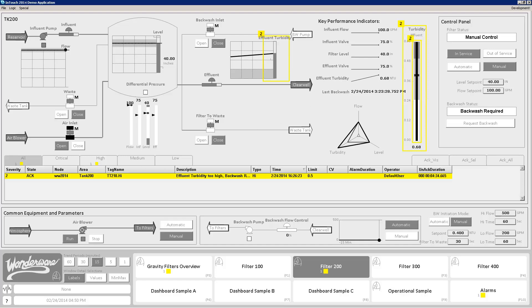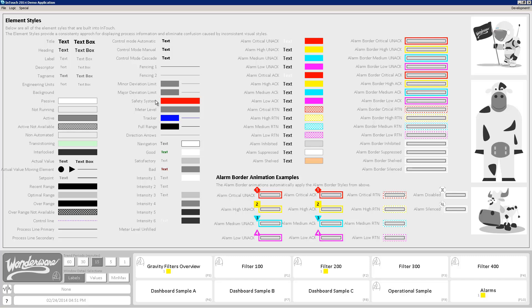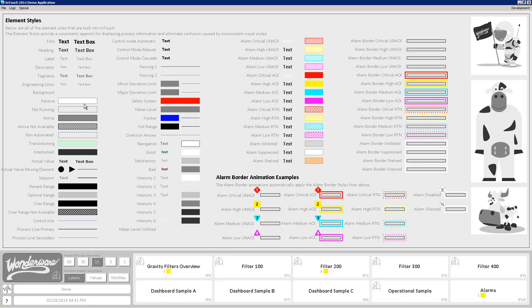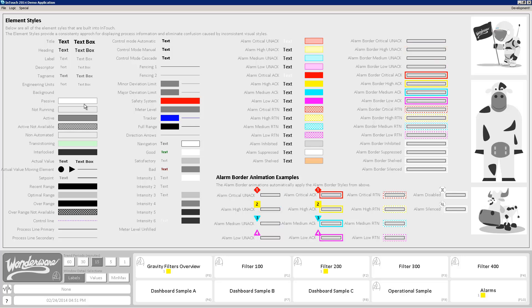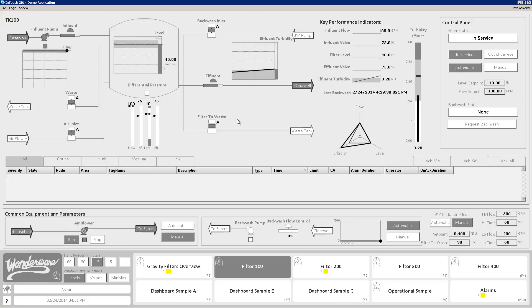We've implemented something called element style, abstracting those colors completely out of the system. When I want to know what 'active' is, active is always this color; passive is always the white color. I apply the styles throughout my entire application to ensure consistency. So when something is in a normal state, I don't have high contrast of color. Some people will say that graphic is boring — and when there is nothing to be done, the graphic really should be boring. It isn't supposed to be exciting to the operator when there's nothing to be done.